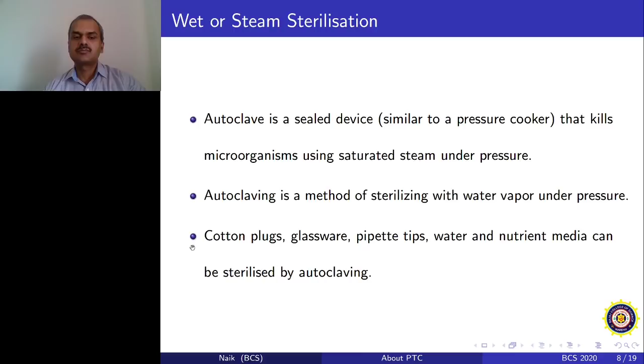Now plasticwares, which are generally made up of polypropylene, polyallomer, Tefzel, Teflon FEP. These are specialized polymers, and that plastic is really hard, and plastic made of these particular branded polymers can be repeatedly autoclaved. Otherwise, if you use a plastic bag or a simple bag which is available in our general grocery market, and you try to autoclave that particular bag, it is going to melt very quickly. So don't use any plastic which is available in a grocery shop, which is not made up of polypropylene, polyallomer, Tefzel and Teflon, as that is not good for wet or steam sterilization.